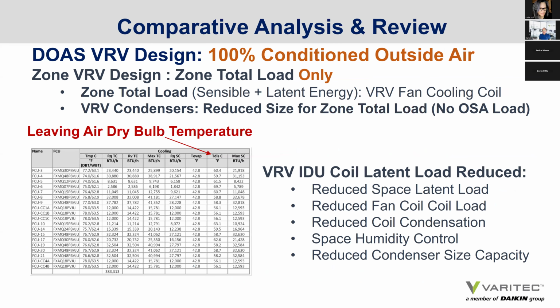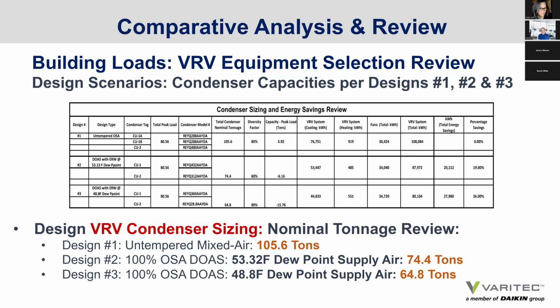Well, if we look at a decoupled 100% outside air solution for variable refrigerant, look at the more relaxed supply air condition off the fan coil units because the outside air component is decoupled from the variable refrigerant fan coil. By using a 100% outside air unit, you're able to use free outside air preconditioning, so your overall tonnage to the building is reduced, and your overall tonnage to the variable refrigerant system is significantly reduced. And these numbers down at the bottom demonstrate that very clearly. With an untempered mixed air variable refrigerant design, you're at 105.6 tons. By using a decoupled DOAS with enthalpy energy recovery, we're now down to 74.4 tons because of the free cooling of the outside air at the DOAS unit.